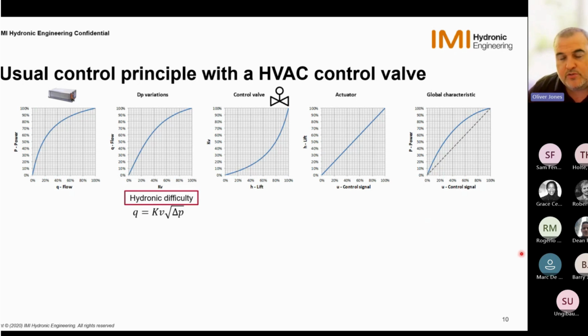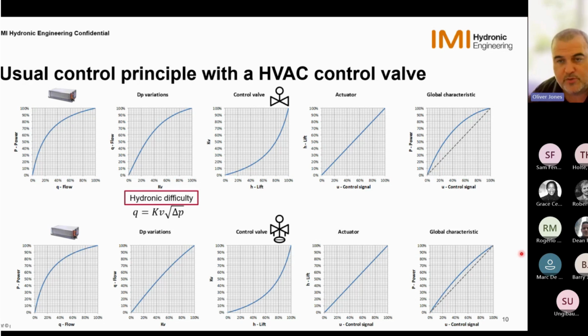So to compensate for the hydronic difficulty, we took a newer approach at first than simply working with standard control valves. So we introduced differential pressure control into the control valve to make a pressure independent control valve with a self-acting DP controller, which is now acting by itself to facilitate the life of the control valve. And the control valve continues to do its work on its KV characteristic. But now the DP controller internally of the valve is absorbing these changes of pressure that are induced by the hydronic network and have flattened this curve to make the valve's life as easy as possible and give us this global characteristic that we can now see at the end. So we are now much closer or tighter to that straight linearity line as possible, and we should achieve a nice and stable room temperature.